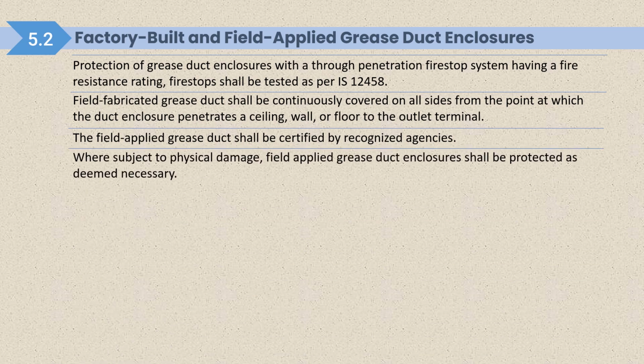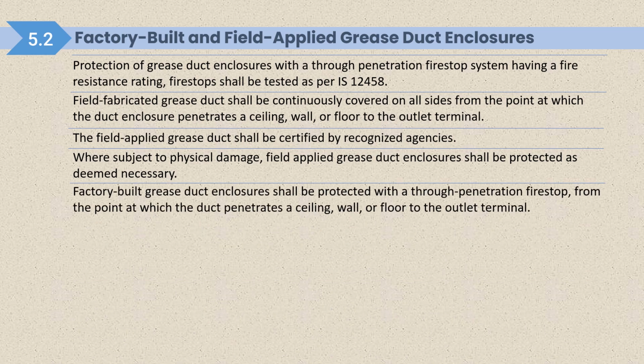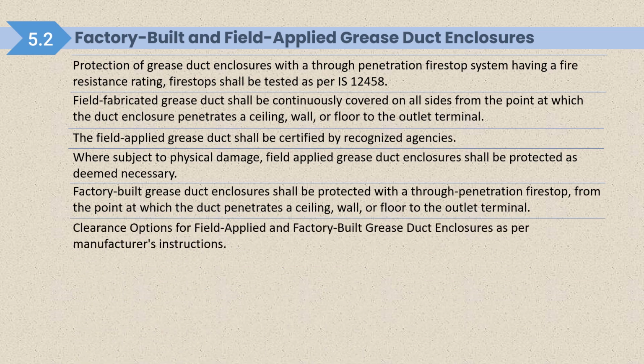Where subject to physical damage, where there is a chance of a duct getting physically damaged, field applied grease duct enclosure shall be protected as deemed necessary. Factory built grease duct enclosures shall be protected with a through penetration fire stop. So wherever there is a chance of leakage, it should be protected by fire stop materials from the point at which the duct penetrates a ceiling, wall or floor to the outlet terminal. If the duct is passing through any ceiling, wall or floor, it should be sealed properly by fire stop materials. Clearance options for field applied and factory built grease duct enclosures are as per the manufacturer's instructions.